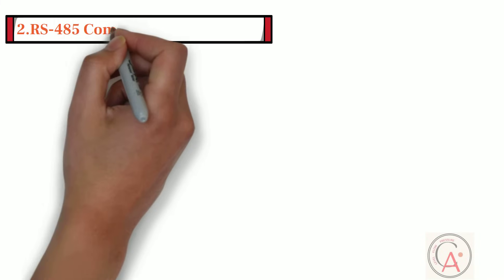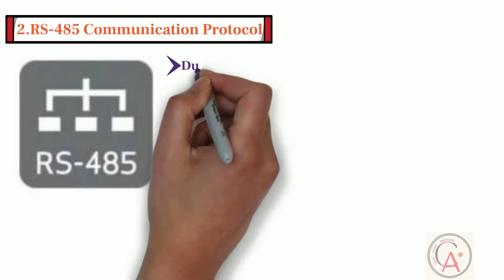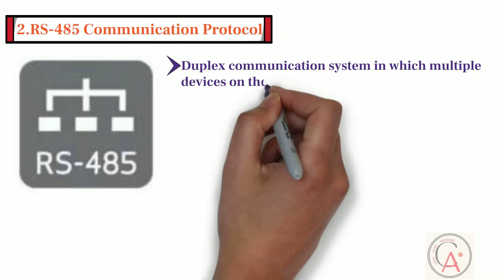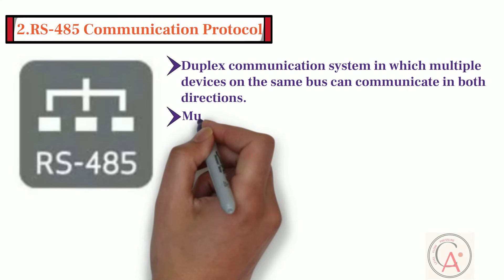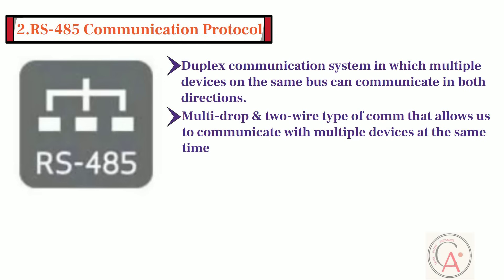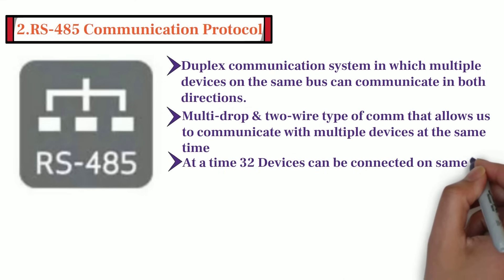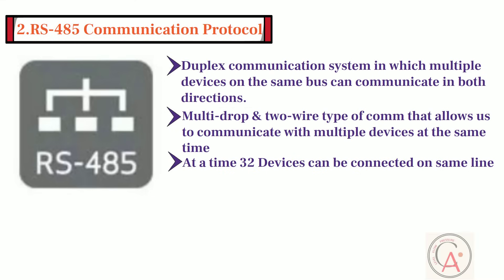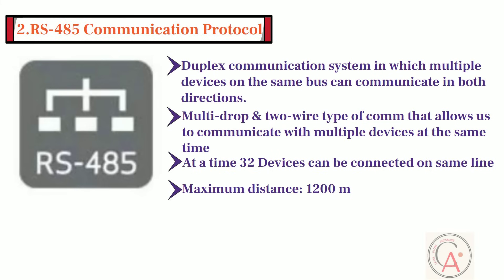Now let's learn about the RS-485 communication protocol. RS-485 is a duplex communication system in which multiple devices on the same bus can communicate in both directions. In other words, RS-485 is a multi-drop, two-wire type of communication that allows us to communicate with multiple devices at the same time. The main difference between RS-232 and RS-485 is that up to 32 transmitter-receiver pairs may be present on the line at one time on RS-485, and a 120-ohm resistor must be used to terminate the main line. It is used in serial communication up to 1,200 meters with 100 kilobits per second speed.